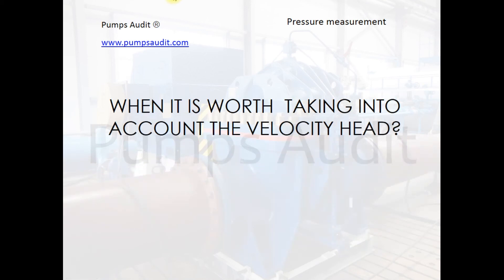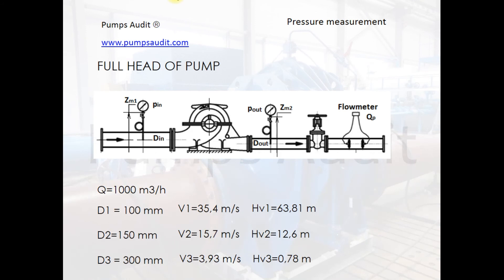One more important question: when is it worth taking into account the velocity head? To answer this, let's calculate the velocity heads for different pipe diameters — 100, 150, and 300 millimeters — for a flow of 1000 cubic meters per hour. For the 100 mm pipe, the velocity is 35 meters per second and the velocity head is almost 64 meters, which is quite a large value. For the 300 mm pipe, velocity is 4 meters per second and velocity head is 0.78 meters. It is clear that for pipes of 100 and 150 mm, the velocity head should be taken into account, while for the 300 mm pipe it can be neglected.